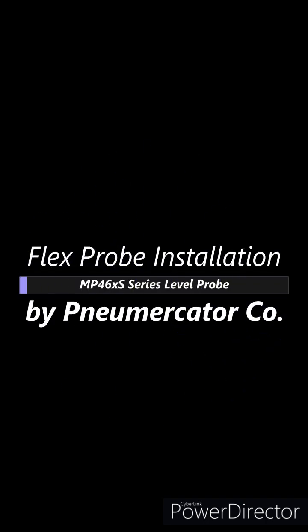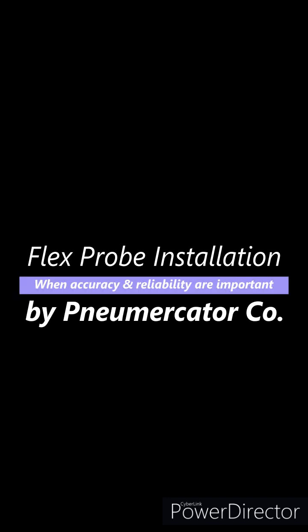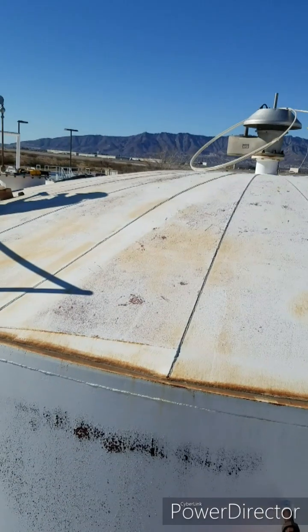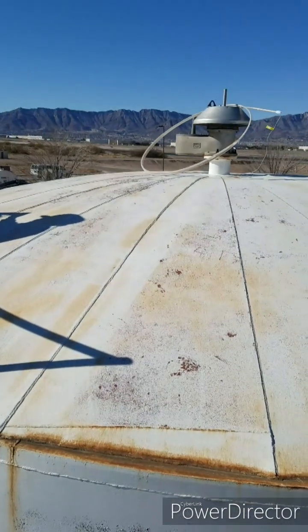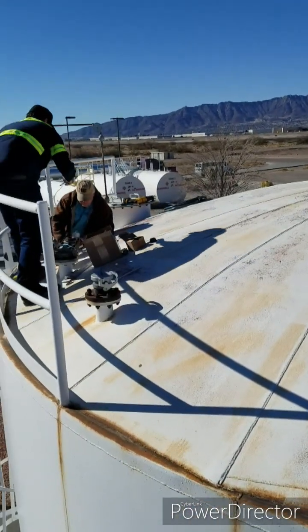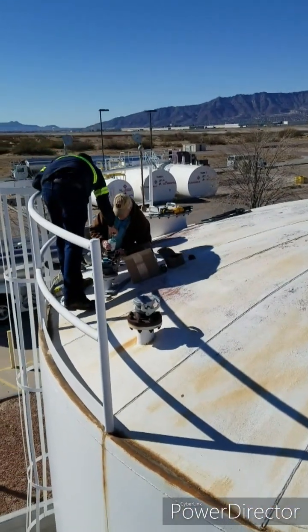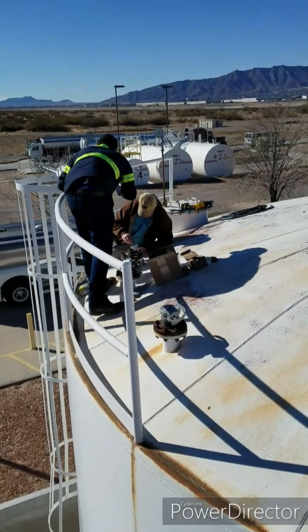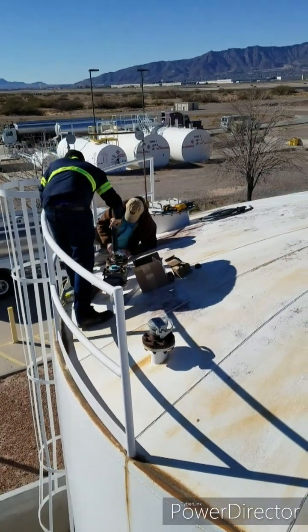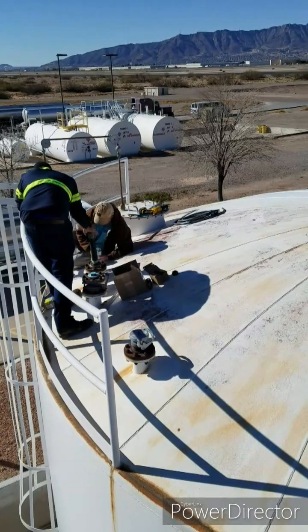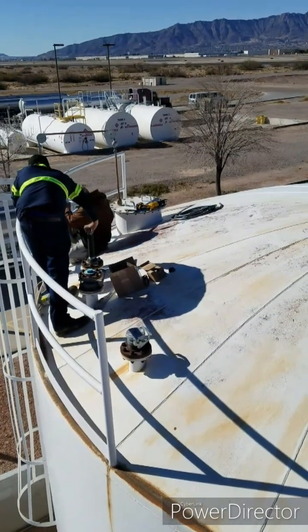This video is not intended to replace the installation instructions which are provided with the product and also available on our website. Please review them prior to your installation. The FlexProbe installation should be done by two qualified technicians familiar with local wiring codes and explosion hazard electrical practices. Having the correct measurements are important in achieving the proper nipple length for mounting the probe. The formula can be found on page 5 of the installation manual for this calculation.